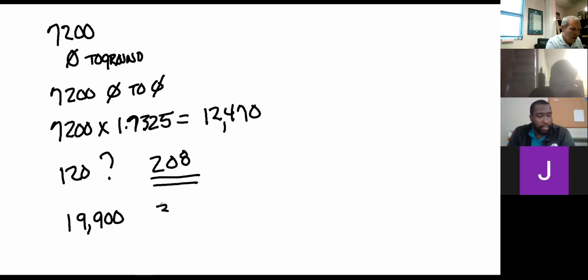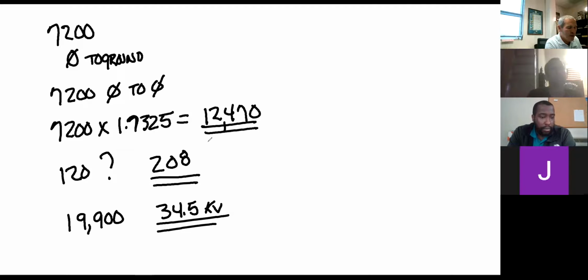34,476.75. We round to 34.5 kV, kilovolts. Yeah, that's what I got. I know you've seen these before. That's where we're getting that calculation from. 19,900 phase to ground. All right, phase to phase, 34,500. Now you know the reason why we just don't add them together is because in generation, we cannot have 2 phases at the peak voltage at the same time.